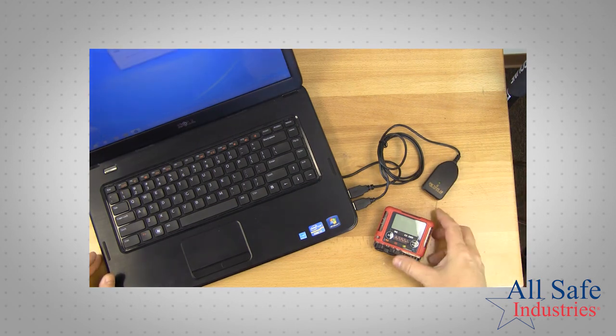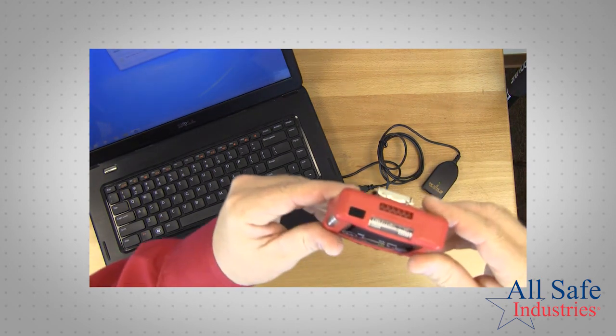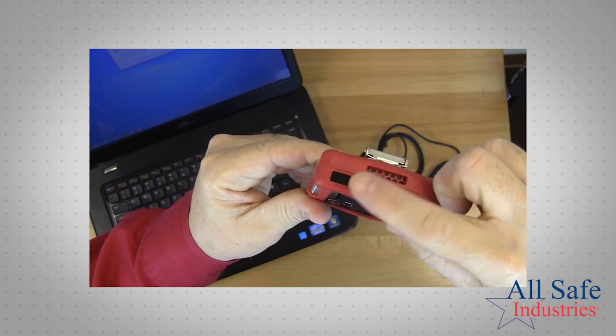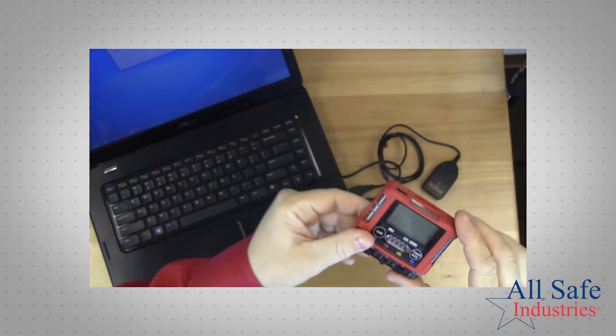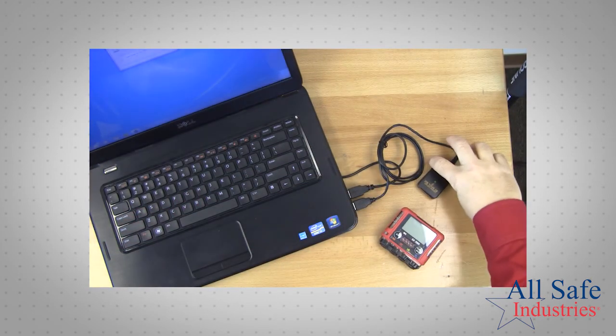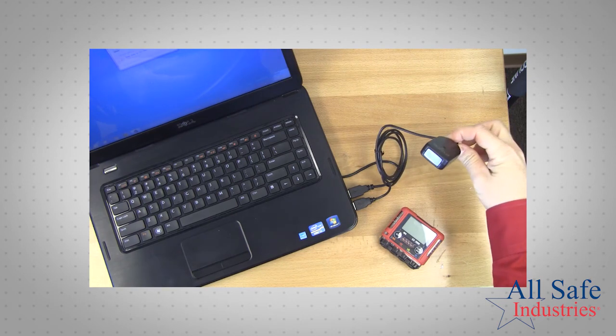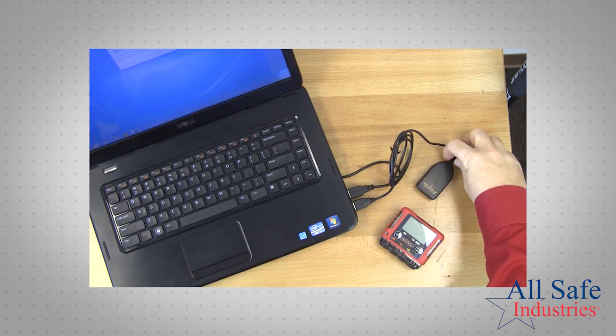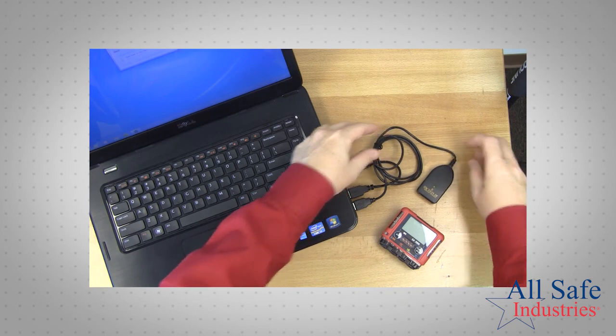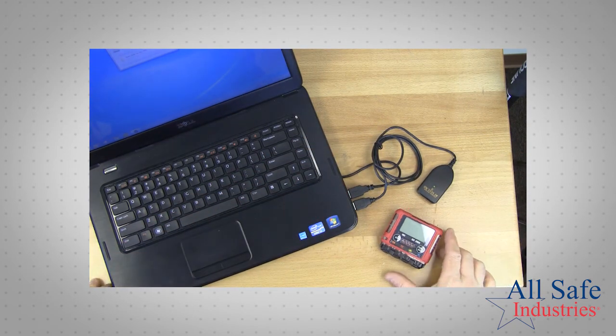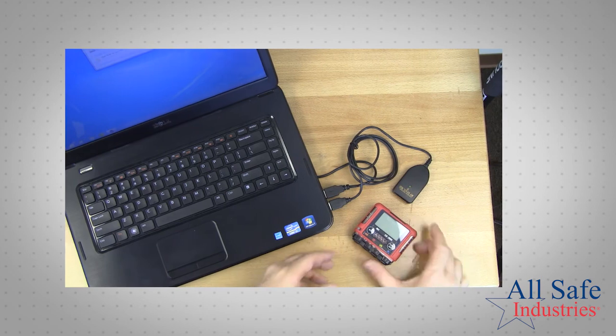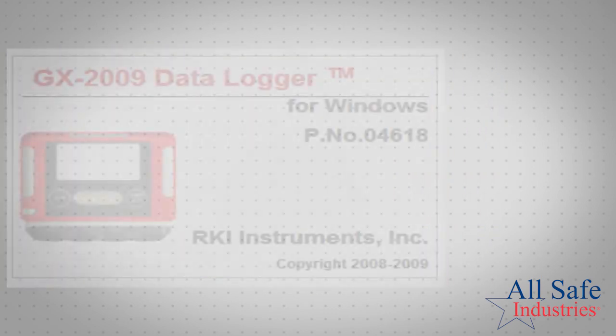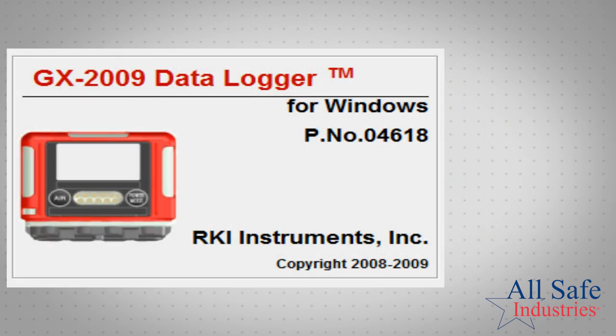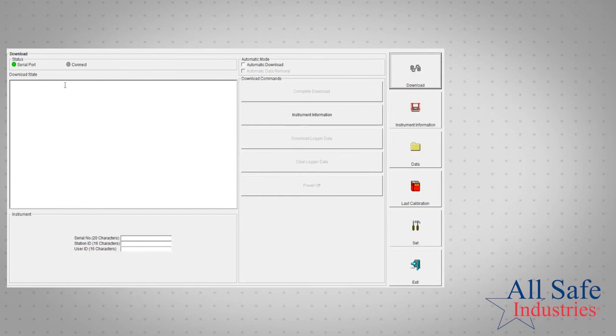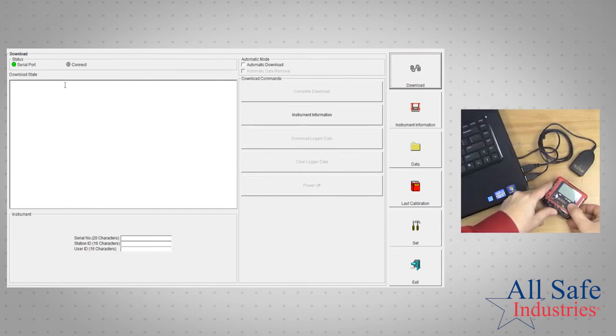These instruments communicate via infrared, so the top port on your instrument is your infrared port, and that needs to be lined up with your infrared port reader that just plugs into your USB. So it just works exactly like your remote control for your television. It communicates infrared. So on your computer, you will launch the GX-2009 program. The Datalogging program will open. Then you'll come and turn your GX-2009 meter on.